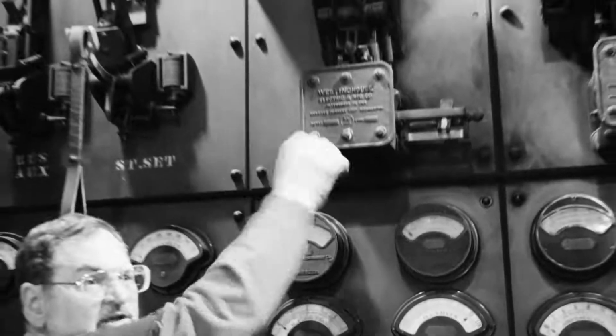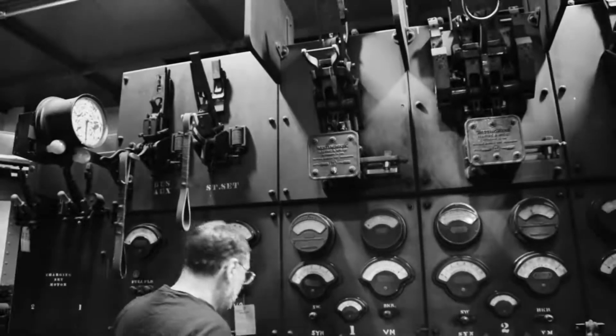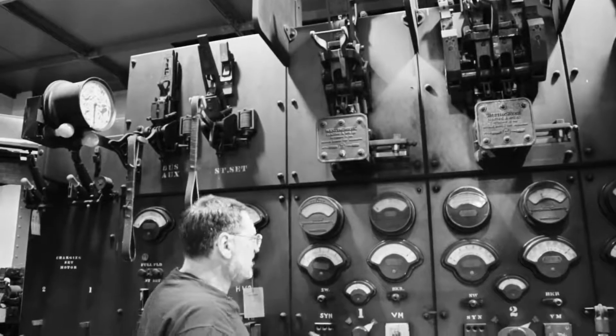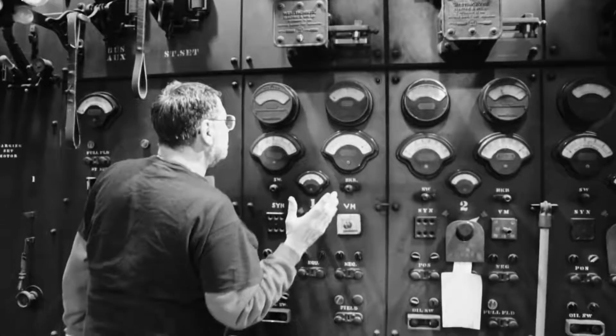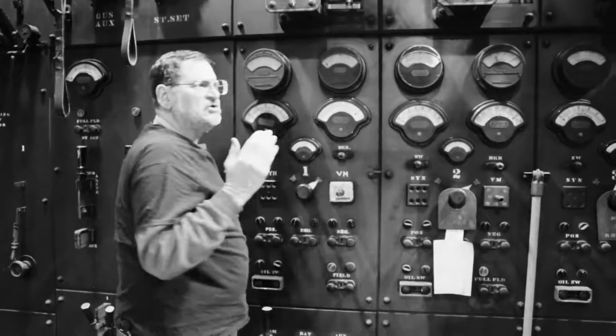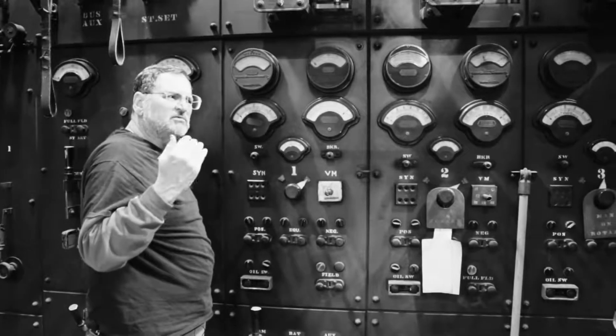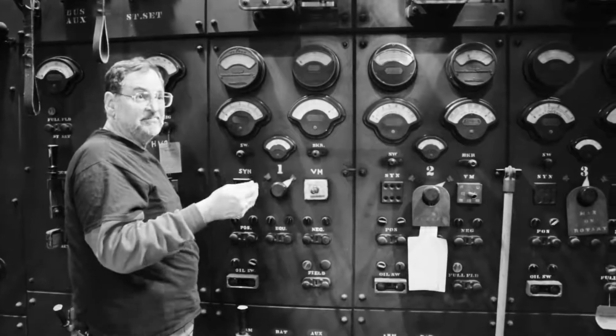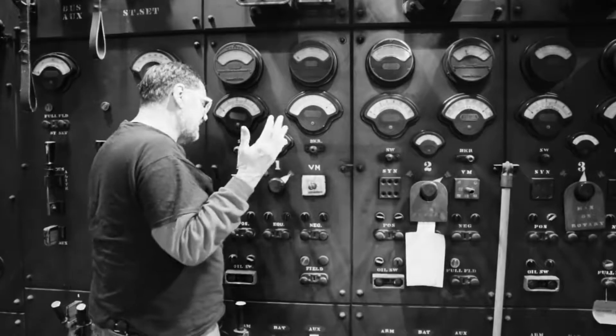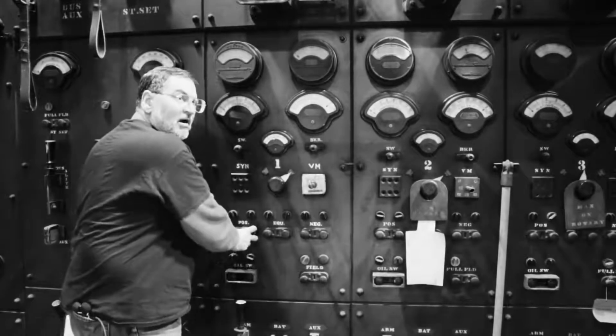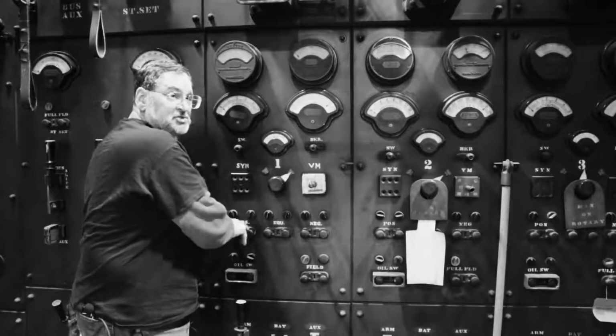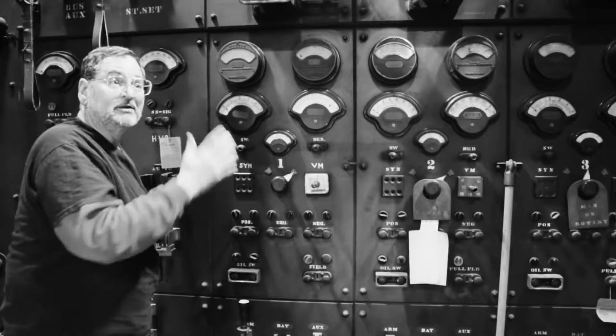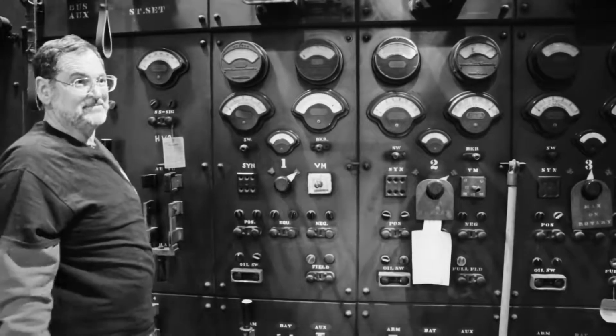I would close the direct current breaker, and that would connect the machine to the bus. And then depending on what the voltage is, we have a differential voltmeter here, and we try to have the rotary about 3 to 5 volts above bus voltage. And then at that right moment, boom, I close the positive breaker in the basement, and the machine is on the line supplying power to the subway.